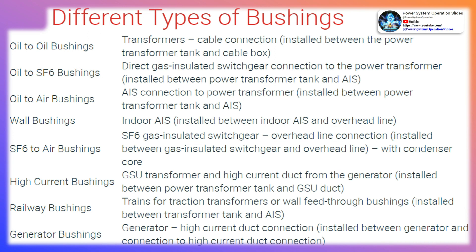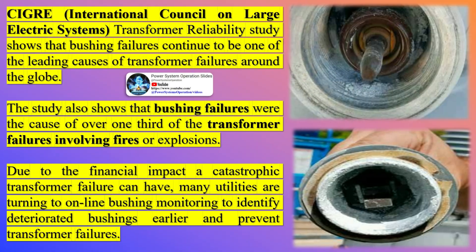How often should we perform online monitoring? Online bushing monitoring is typically a continuous process. The system monitors the condition of the bushings continuously, providing reliable and unambiguous condition assessment. This allows for early detection of faults, and action can be taken before the transformer is damaged. However, the frequency of offline tests, which are performed in addition to online monitoring, may vary, and are often performed on a routine schedule, perhaps once every few years.